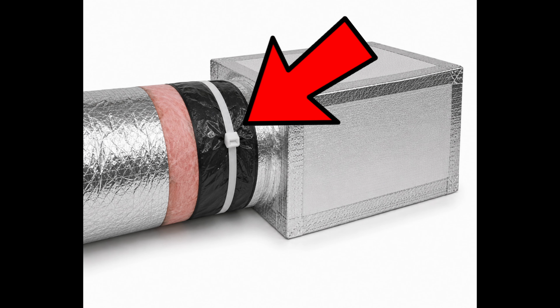Well, I've experienced situations where I go up in an attic and I notice that there's mold growing in the area where the mastic is. And the cause of that problem would be improper adhesion of the tape to seal off any type of air leakage. And a lot of times that happens because, number one, the tape wasn't properly adhered. But the most important thing is that the flexible duct wasn't properly butted up against the actual box with the insulation. So that means it left a little gap with just a black part. Well, if you don't have that insulation all the way up against the box and properly taped, it could cause condensation. But then the condensation plus the little gap that was left causes the air to leak out. Therefore, you have leaking air into your attic. And then it causes issues with moisture and mold growing onto the box. And mastic is not great at repelling mold, at least in my experience or when I used to do it. So it needs to be properly done.